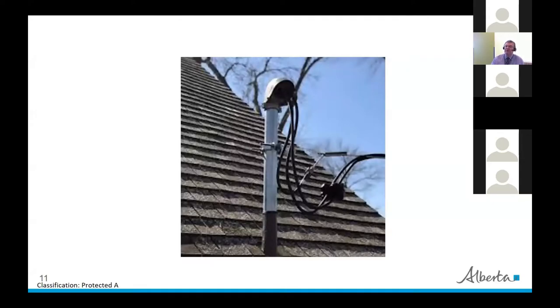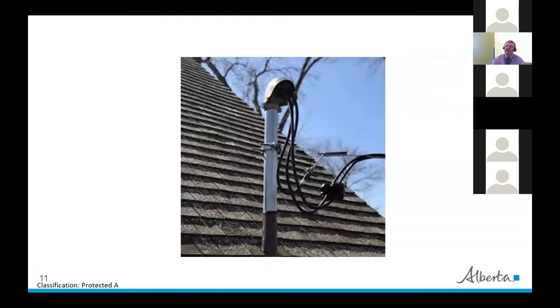Here's a typical example most people are familiar with. If you look at a house, you see the electric service coming in — a weather head and conductors coming in from the utility. There are connections there, and then wires coming out from the weather head that are part of the consumer's equipment. On the consumer side everything is regulated by the Canadian Electrical Code Part 1, whereas on the utility side everything is regulated under the utility code.